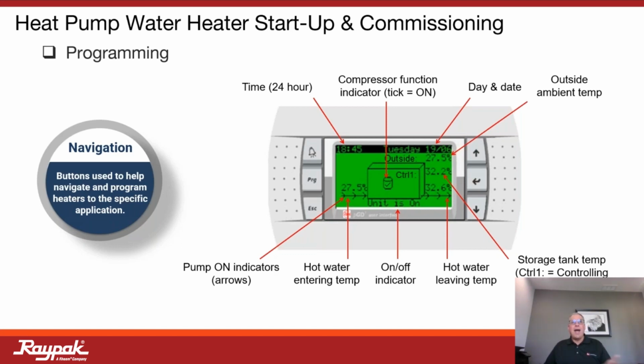And we know that if we pipe this and plumb this correctly, we should see a very narrow temperature rise across that unit. Again, this is a multi-pass system. We're circulating cool water in via that compressor. We're extracting heat and sending it right to the tank in multiple passes. So anywhere between a 5 and 8 degree rise across this unit will be able to be displayed here. And again, we'll change this back to Fahrenheit. So we can see that we have maybe 130 degree water going in, 138 degree water going out into that storage tank, trying to satisfy set point.